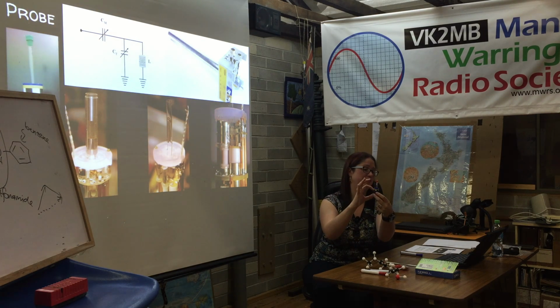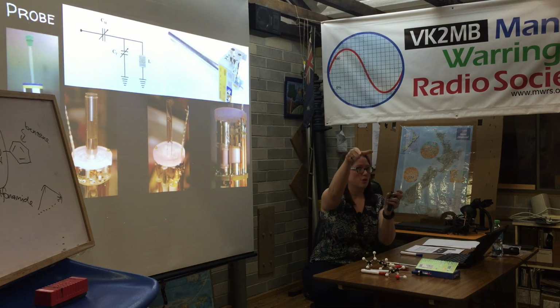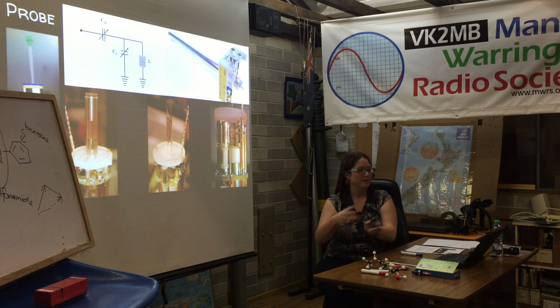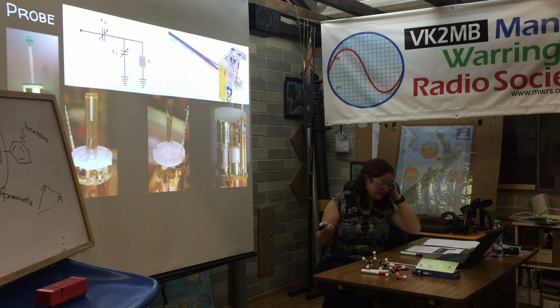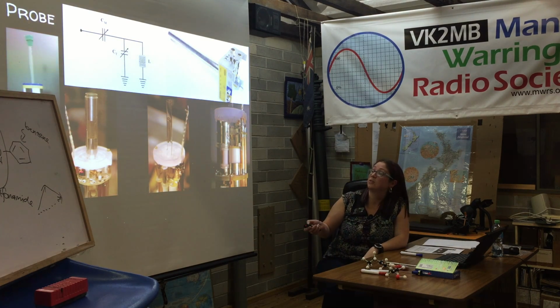Also the position of the spinner on the tube controls what level the tube sits in the probe, so it sits right in the correct region of the coil. We want to be able to just drop that in from the top. We don't want to have to muck about taking the probe out and sticking it in sideways or anything like that. So we don't use solenoids perpendicular to the field in solution state. You do in solids, mostly-ish. So we use either a saddle coil or a Helmholtz coil orientation.